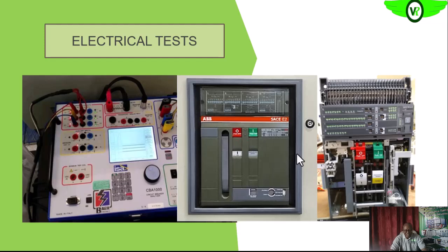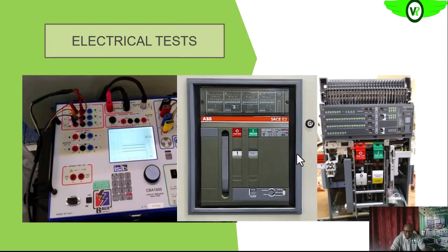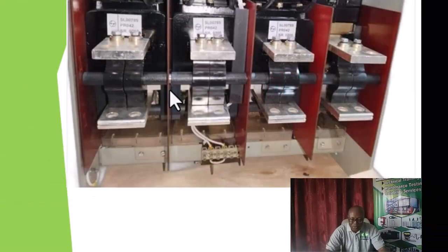So next we want to look at the electrical tests that we can carry out on the medium voltage air circuit breaker. Remember, when we say medium voltage, we are talking of voltage that is above 1 kV, that is 1000 volts, between 1000 and about 60 kV. So the electrical tests will basically include resistance measurement on bolted connections, as we used to do.